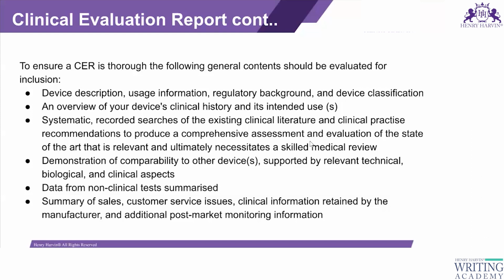Then data from non-clinical tests summarized. So in case non-clinical tests or non-clinical studies are conducted in case of medical devices, the data obtained from the non-clinical studies is to be provided. Then a summary of sales, customer service issues, clinical information retained by the manufacturer, and additional post-marketing monitoring information.